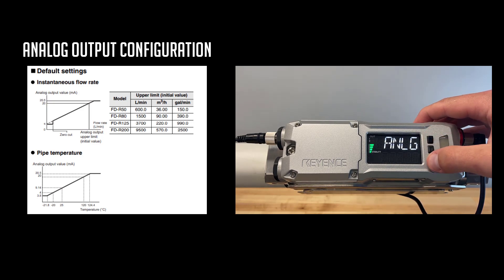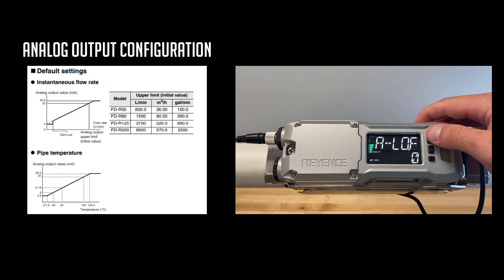Once selected, tap mode one more time. You can see our A-Low value, which is our 4 milliamp or 0 milliamp value. We can cycle that to whatever we need our scale to be. Tap mode one more time. You should see A-High, which is your 20 milliamp value. And again, you can scale this to whatever value you need, so that your PLC or analog input device recognizes that scale of the FDR.